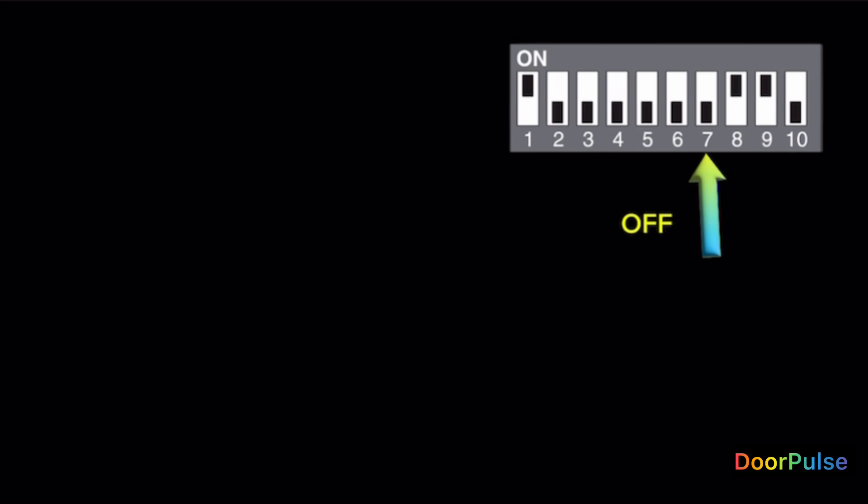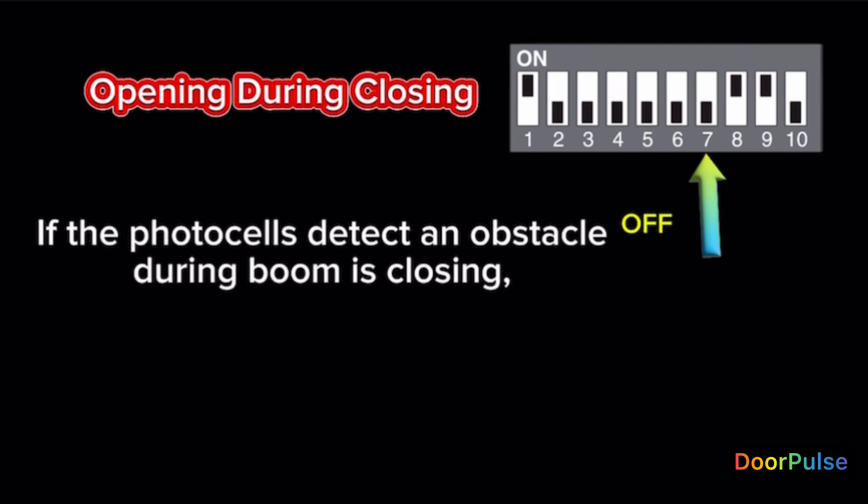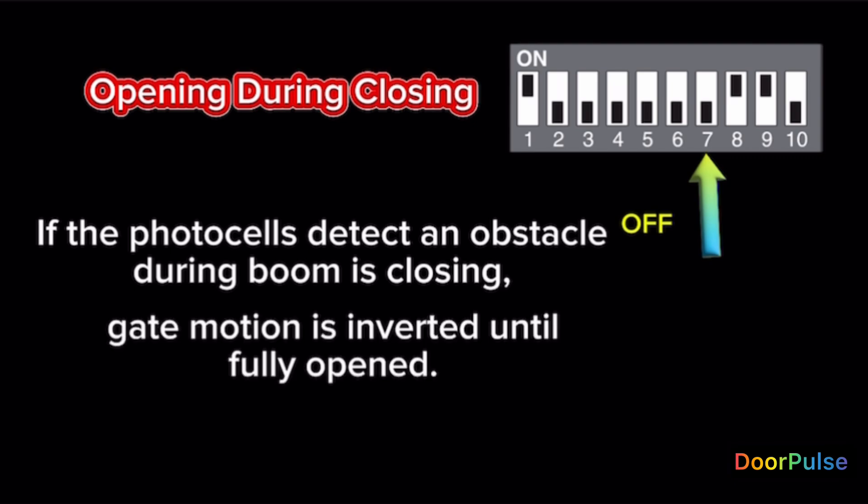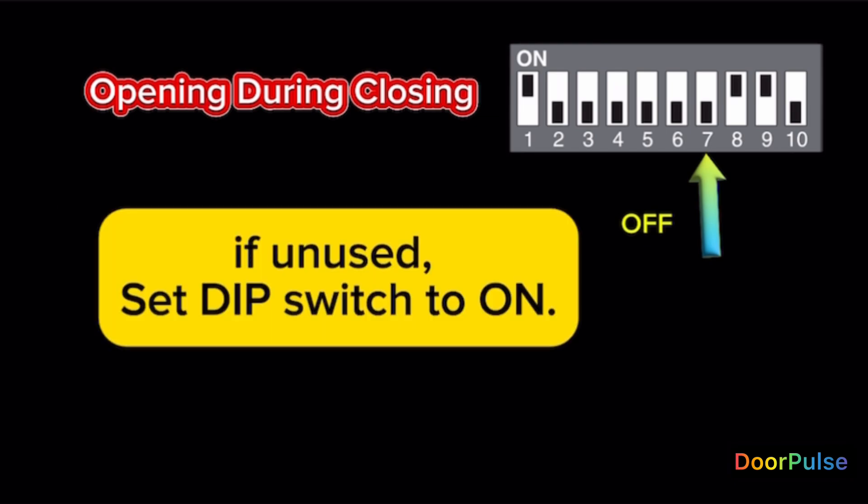Switch 7 OFF. Opening during closing. If the photocells detect an obstacle during boom is closing, gate motion is inverted until fully opened. Connect the safety device to terminals pin 2 and C1. If unused, set DIP switch to ON.